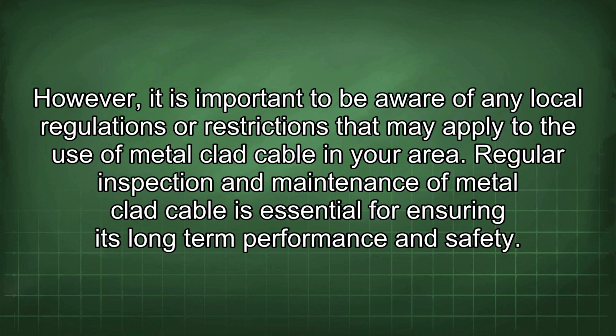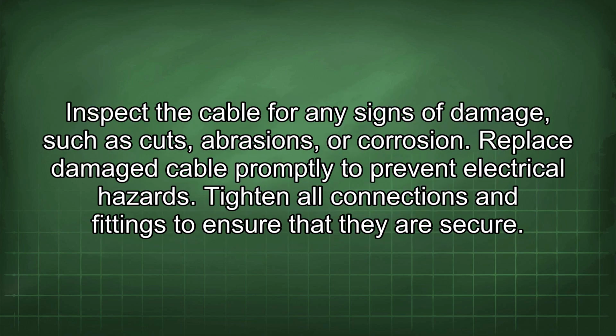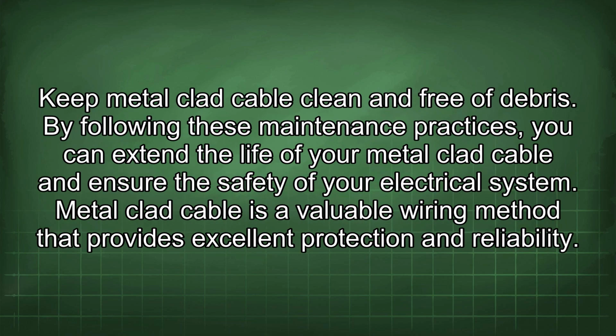Regular inspection and maintenance of metal-clad cable is essential for ensuring its long-term performance and safety. Inspect the cable for any signs of damage, such as cuts, abrasions, or corrosion. Replace damaged cable promptly to prevent electrical hazards. Tighten all connections and fittings to ensure that they are secure. Keep metal-clad cable clean and free of debris. By following these maintenance practices, you can extend the life of your metal-clad cable and ensure the safety of your electrical system.